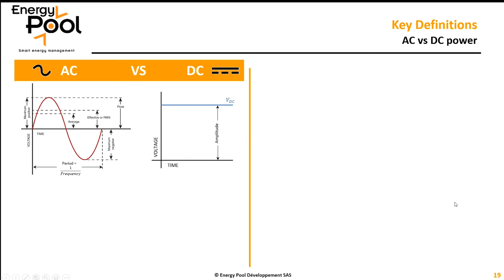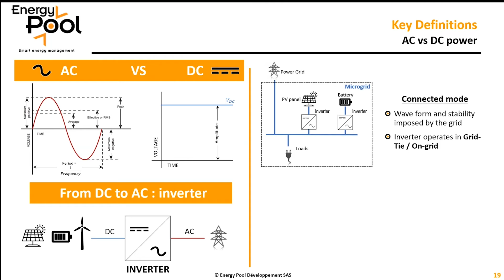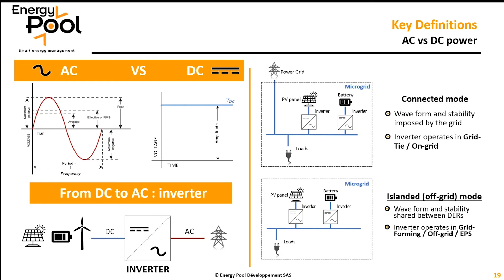An inverter can operate in different modes. When we are talking about connected mode, the power grid will impose the voltage waveform, so it will impose frequency and peak value. And the inverter will operate in the so-called grid tie or on grid mode, which means that it will reproduce exactly the voltage and the peak value imposed by the power grid. When we are talking about islanding mode, the power grid is no longer there to impose stability on the waveform, and it has to be shared between the distributed energy resources. In this case, the inverter should operate in the so-called grid forming or off-grid mode, or sometimes we also call it the emergency power supply mode, where the inverters are able to impose and to create the waveform of the voltage.